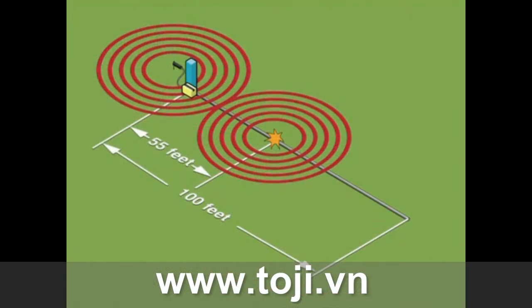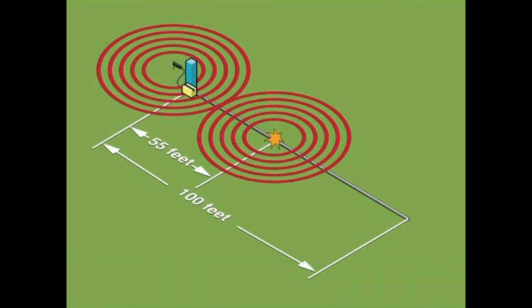If this signal level does not fall within 12 dB of the reference reading, there may be multiple faults on the line. Sometimes you will be fault locating on very long sections or in very bad soil conditions, and the fault signal pools may not overlap each other across the entire section of cable. You must be within one of these pools in order for your equipment to detect the direction of the fault. For example, you have a section of cable that is 100 feet long. There is a break in the insulation of this cable, causing an earth return fault at 50 feet. It is very likely that the areas of detection, or pools, will overlap on this short section of cable. You would never know that you have passed from one area of detection to the other.